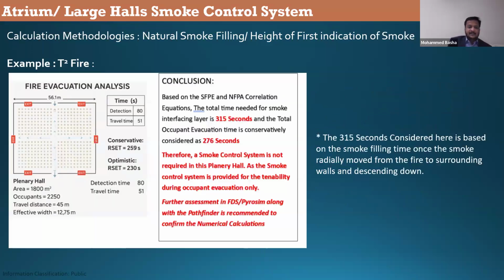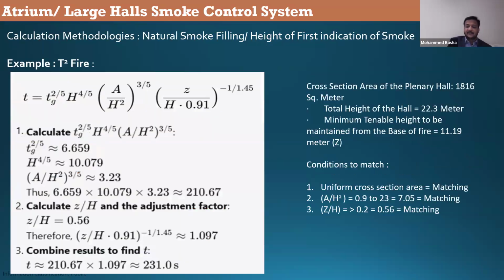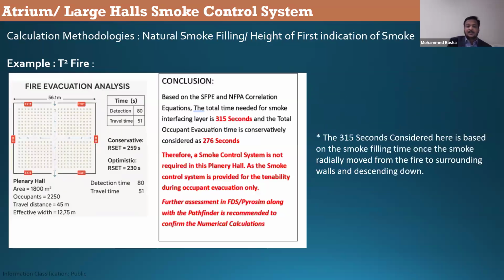So an evacuation analysis is considered for the same area. The evacuation formulas are based on Society of Fire Protection Engineers and NFPA correlation equations. The total time needed for the smoke interface layer is 315 seconds. Why did I mention 315, whereas I'm showing 231 here? Because 231 seconds is the smoke descending time, whereas the smoke has to rise first up to the 20 meters, which is called thermal movement, from the floor level to the ceiling level. Then from the ceiling, it has to go radially to the side wall. Then only will it start to descend.